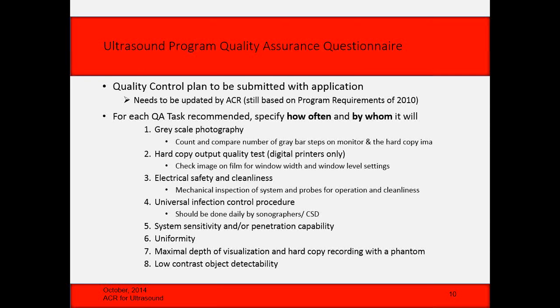On the breast ultrasound program, the QA questionnaire, as I mentioned earlier, is a little different. It actually has been revised, but they didn't quite get it right. It still doesn't exactly match the annual survey QC test, which I believe they intended to do. I actually have asked the ACR for clarification on that as to whether they intended it to be slightly different or not. There's 12 activities recommended for the QC plan, so you might guess, or assume, I should say, that when the ultrasound program questionnaire gets updated, it's probably going to have 12 activities that look a lot like these.